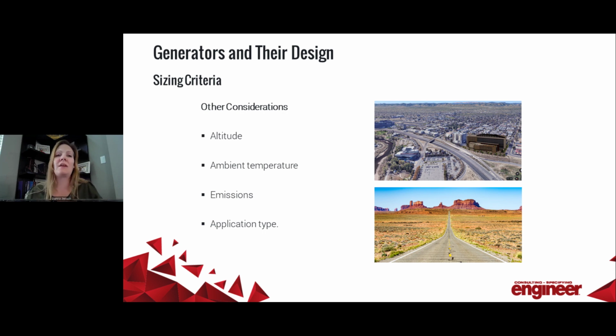And then it should not go without saying, with all of this talk about increasing the alternator size, you do need to take into account what the environmental aspects or the emissions are going to be associated with those larger engines. As James discussed earlier, you're going to deal with different tier ratings based on the size of the engine that you pick. So it does warrant special considerations in the sizing aspect of the system. And again, James also already discussed the application type that could impact your loads. So if the generator is rated for continuous duty and planned for long periods of runtime, well, it must be much more robust and be able to handle those temperature rises and load fluctuations to last for longer periods of time, as opposed to a standby engine, which may not operate nearly as long or nearly as much throughout the year.